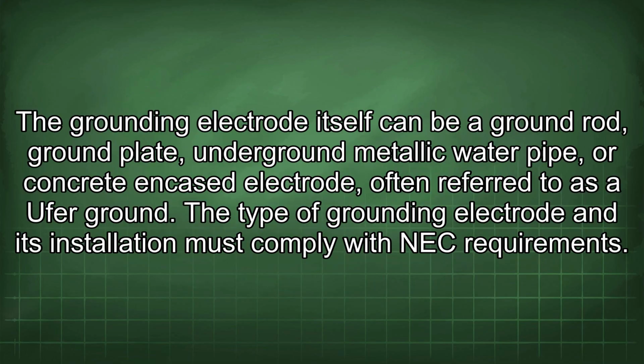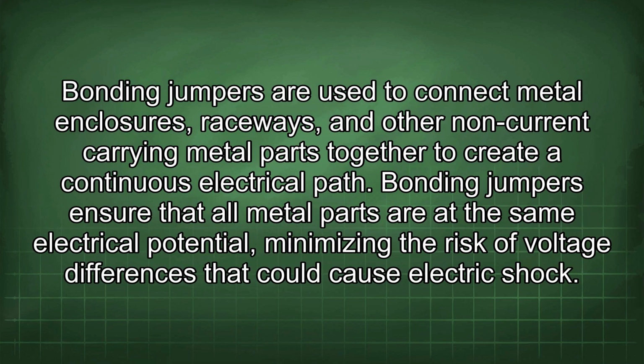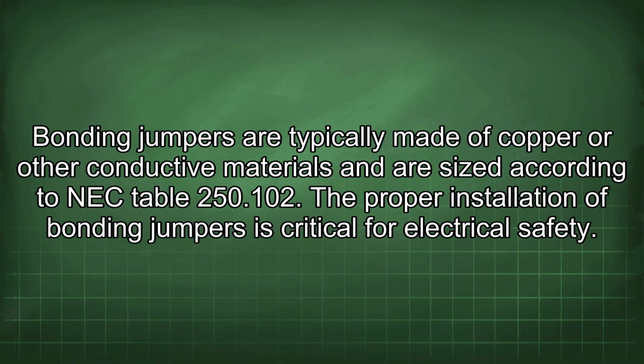The grounding electrode itself can be a ground rod, ground plate, underground metallic water pipe, or concrete encased electrode, often referred to as a UFER ground. The type of grounding electrode and its installation must comply with NEC requirements. Bonding jumpers are used to connect metal enclosures, raceways, and other non-current carrying metal parts together to create a continuous electrical path. Bonding jumpers ensure that all metal parts are at the same electrical potential, minimizing the risk of voltage differences that could cause electric shock. Bonding jumpers are typically made of copper or other conductive materials and are sized according to NEC Table 250.102. The proper installation of bonding jumpers is critical for electrical safety.